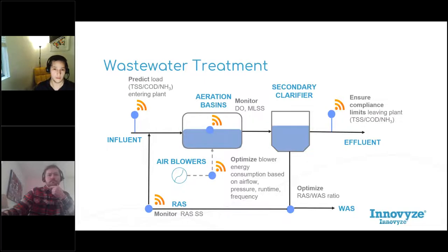For us, it was four milligrams per liter. With that alone, and creating that self-adapting model and process schematic, they were able to get new daily schedules on how to do that, which reduced their cost an additional 20% on chemicals alone. For systems like that, it's relatively imperative to have some of that live, real-time data, because often what we find is causing excessive spend, whether in energy or chemical dosing, is that we don't really have the capability as operators.